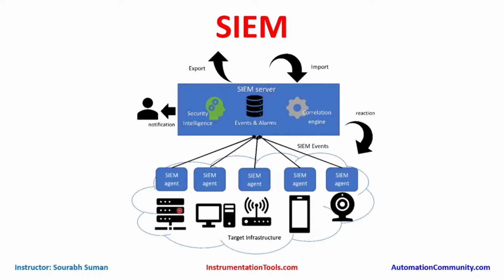In an OT system, we need to take approval of the OEM prior to installing any agent or changing any service or any DLL file, even on the servers, workstations, or HMI. With the vendor or OEM, we can discuss how much data, bandwidth, CPU resources, and hard disk it will consume. We need to see all those things prior to putting an agent on any system. Some monitoring systems can have an agent if it is approved by the vendor and it is not in a time-sensitive network, where degraded performance of that system or switch could directly cause production loss.